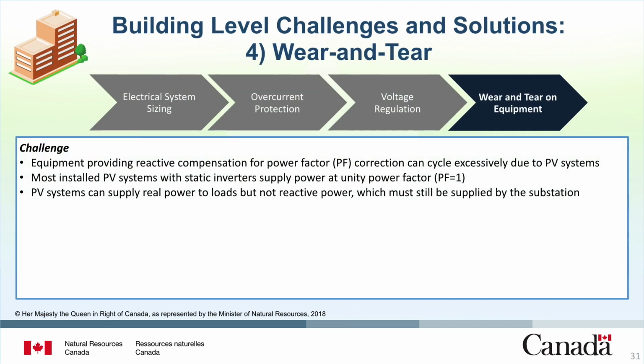For the last section on building level challenges and solutions, we will discuss wear and tear on equipment. Equipment used to actively provide reactive compensation for power factor correction can also cycle excessively due to high penetration of intermittent renewable energy generators. The reason for this is that most installed PV systems with static inverters supply power at unity power factor, or PF equal to 1.